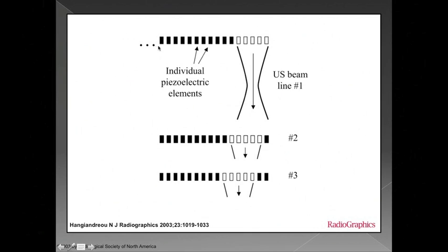In linear transducers you have many more individual piezoelectric crystal elements, and instead of utilizing interference patterns and firing them all at the same time, it actually selects a subset of crystal elements that are physically located next to each other in the ultrasound array, fires those sequentially to form the first beam line, then shifts over one for the second, and shifts over another for the third, and so on for the entire length of the array.